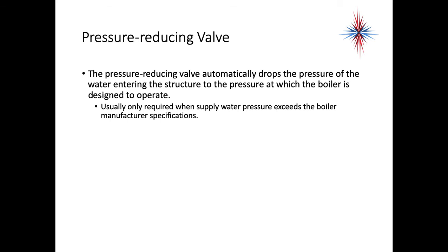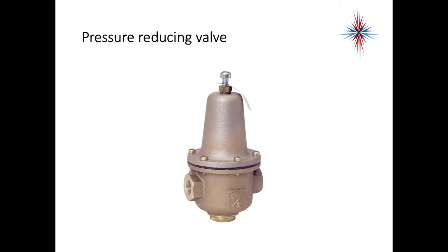The pressure-reducing valve automatically drops the pressure of incoming water to the pressure at which the boiler is designed to operate. Boilers operate between 12 and 15 psi, while building supply pressures are normally between 60 and 100 psi. The screw at the top allows you to adjust to the needed boiler pressure. Always watch the arrows — they indicate the required direction of water flow.